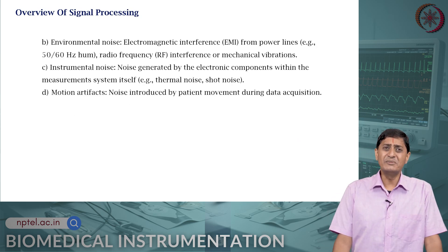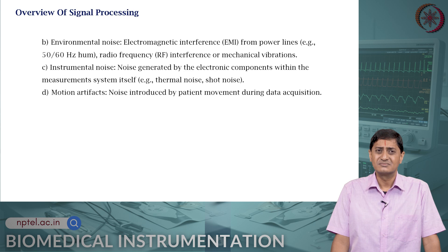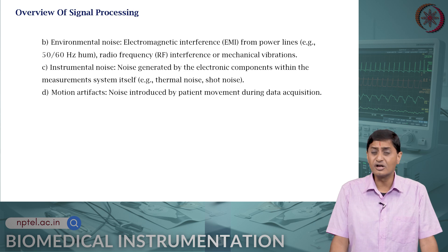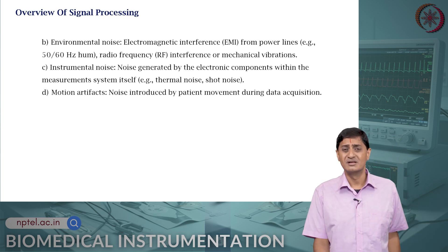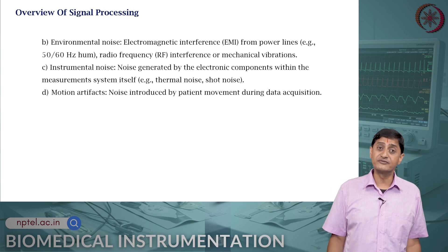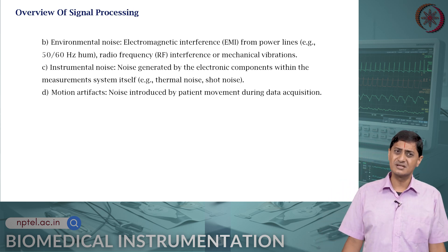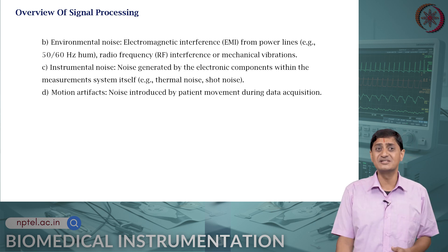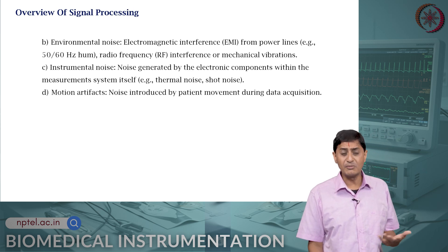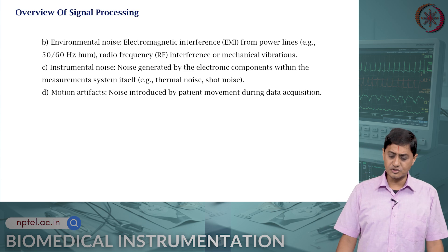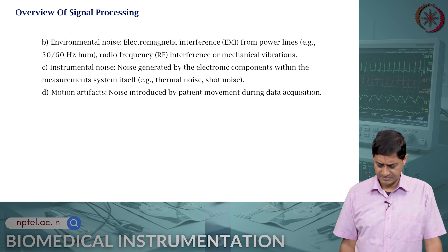Then there is environmental noise: electromagnetic noise, hum of the AC at 50 or 60 hertz, RF noise, mechanical vibrations, and other measuring or therapeutic devices in the ICU — all these can cause electromagnetic interference or noise. And then instrumentation noise — noise generated by electronic components within the measurement system itself — that is thermal noise, shot noise, and motion artifacts introduced by patient movements during data acquisition.